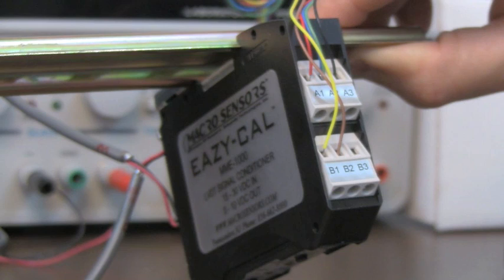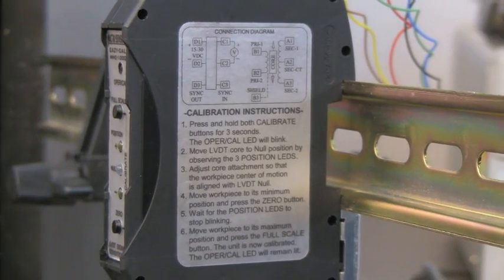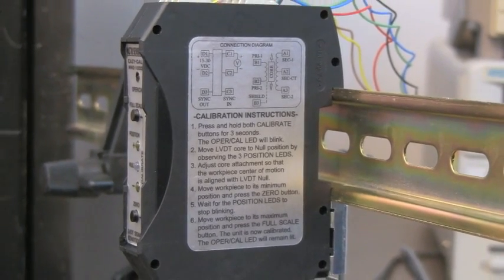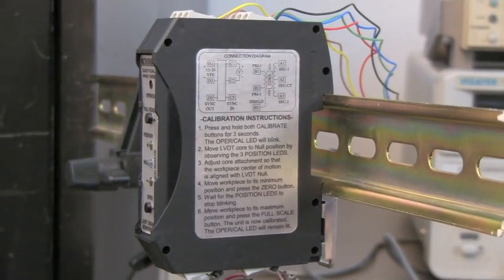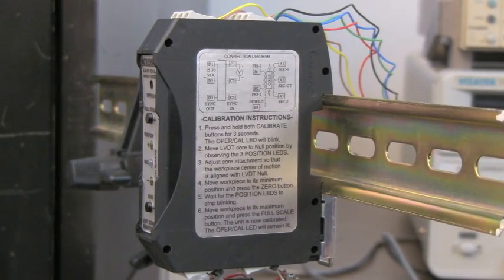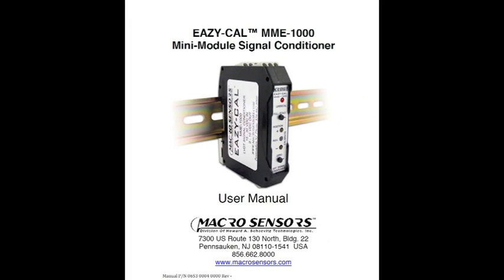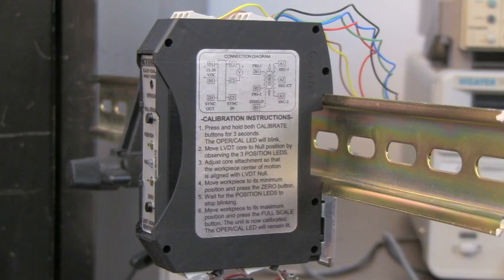If you are using an LVDT which has a shielded cable, the shield may be connected to terminal B3, but is not necessary. A full wiring diagram can be found on the label located on the side of the EAZY-CAL, along with complete calibration instructions for easy reference. In addition, each EAZY-CAL is supplied with a user's manual which contains additional information on calibration, LED lamp functions, electrical specifications, dimensions, mounting instructions, and other helpful notes and tips.